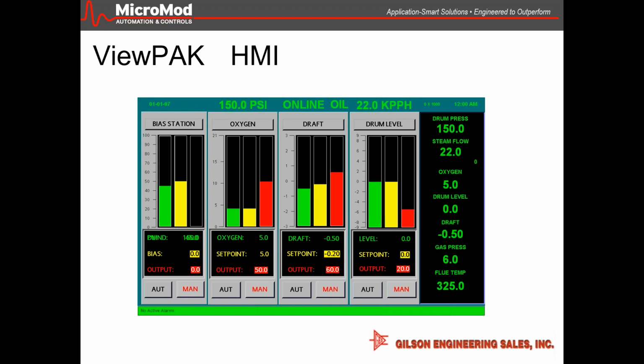You have that documentation and the programming all in a nice, concise document that you can have. It also comes with a termination drawing, a little different than what you're used to seeing. It's not just a termination drawing of the back of the 353 Retro Pack—it's also the drawing of the 352 or 353's back. So you know that you take it off of terminals B19 and 20 and put it on the MicroMod's terminals 21 and 24. Essentially, you can tape this up behind the panel if you're the installer, and you can sit right there and move them from one to another.